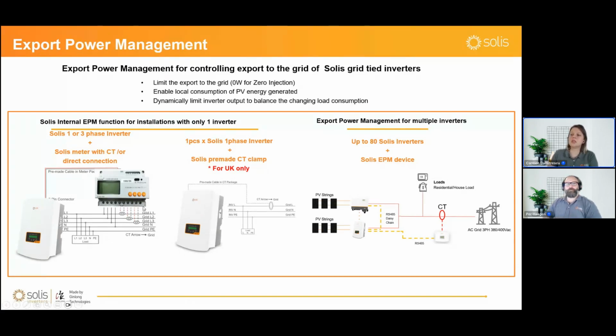So in this case, where we have just one inverter connected to the grid, we can easily use a smart meter. Solis has a type of smart meter which has been specifically programmed to work and communicate properly with inverters. So there's no need for any additional setup on the meter side, only on the inverter side, just to tell it how much energy you are allowed to export to the grid.